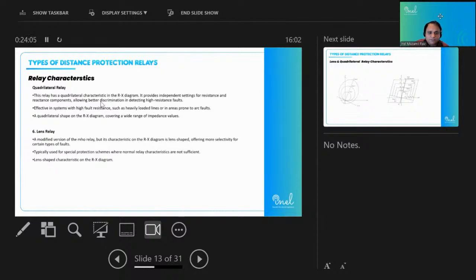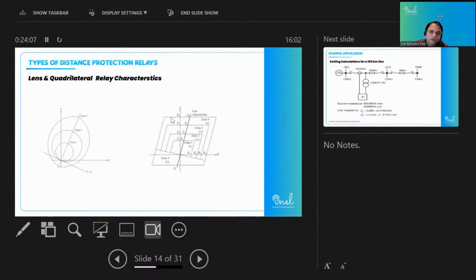So how does it look? This is the quadrilateral relay characteristic. In this, we have freedom to select. This is R1, which is the resistance reach of zone 1, and this is X1, which is the reactance reach of zone 1. Similarly, R2, X2, and R3, X3. These are looking in the forward direction, and this is zone 5, which is actually looking in the reverse direction. This will protect your bus bar and also a portion of the bus bar towards the substation.